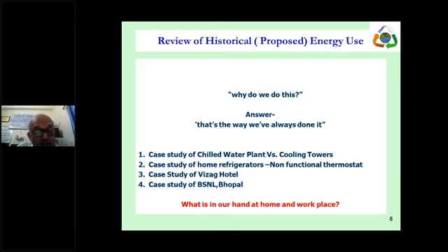So when I checked, I saw that the compressor connected to the 125 kilowatt motor was actually consuming less. It was consuming 59 kilowatt, and the other one was consuming 68 kilowatt. So there was a 9 kilowatt difference, though the connected motor was bigger, because of the inefficient compressor.